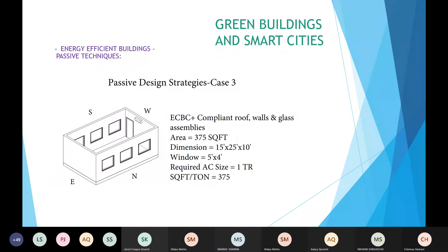So we always tell clients that instead of focusing on costly, high-value, super-efficient AC brands or technologies, you should first focus on passive design strategies. This is something the architect and your air conditioning engineer need to work closely on - the architect will know the benefits of doing this, but won't have the maths for each case. Your air conditioning person working with the architect can tell you which side needs more expensive glass due to greater heat gain, which wall needs insulation and how many inches, and then calculate the exact reduction in tonnage, as shown in these two cases. They can then calculate how much money is saved on air conditioning versus how much is required for the measures taken, giving you the ROI or payback period of what is being done.